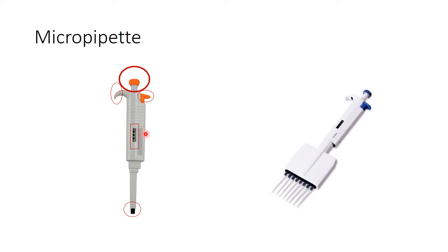Depending on the mode of working, these two are semi-automatic. There are automated or electronic versions of micropipettes too. And depending on the volume, micropipettes may be fixed or variable. That means some range of volume may be displayed like 10 microliter to 100 microliter or 100 microliter to 1000 microliter. This type of micropipette can aspirate any volume ranging from 10 to 100 or 100 to 1000. Fixed means it can aspirate only one particular volume like 500 microliter. So, there are three classifications of varieties of micropipettes depending on the mode of action, number of channels and the volumetric display.